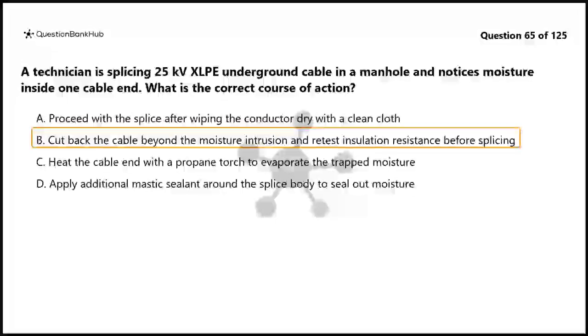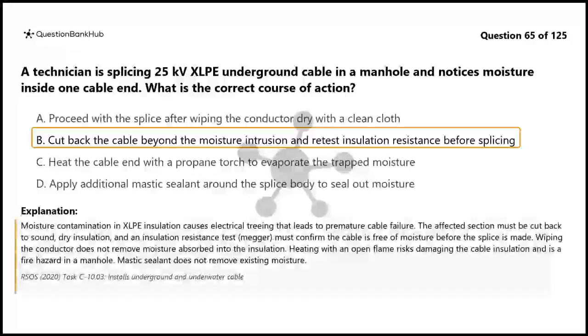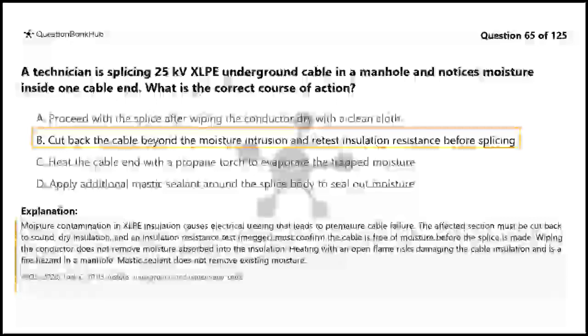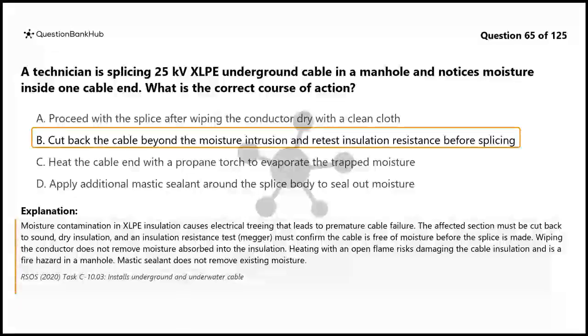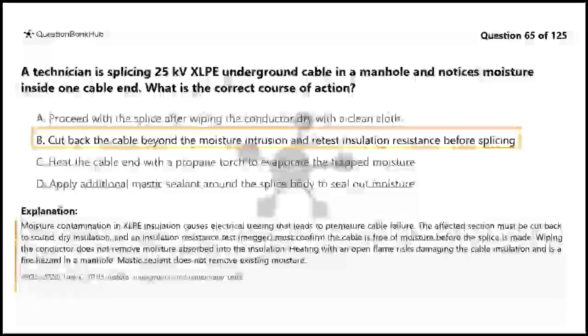The correct answer is B. Moisture contamination in XLPE insulation causes electrical treeing that leads to premature cable failure. The affected section must be cut back to sound, dry insulation, and an insulation resistance test, megger, must confirm the cable is free of moisture before the splice is made. Wiping the conductor does not remove moisture absorbed into the insulation. Heating with an open flame risks damaging the cable insulation and is a fire hazard in a manhole. Mastic sealant does not remove existing moisture.